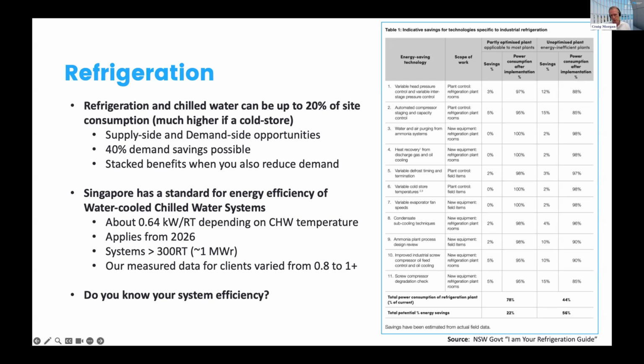Another good example, I haven't got a chart here, but we measured a bunch of chill water systems and water-cooled chill water systems. Singapore love a good standard. They have set a standard, and they've set a standard for how you measure these things. And for large systems over about a megawatt of refrigeration, the target delivered through existing technology, known technology, and good control and management and good system design, not any more expensive than a badly designed system if you were putting it in new. The target is around 0.64 kilowatts per RT for a system delivering, say, 6 degree, 7 degree chill water. Most of the systems we measured delivering that temperature were at 0.8 to 1.2 actually. So we know when you put measurement on these things, they are not operating as efficiently as they could be.